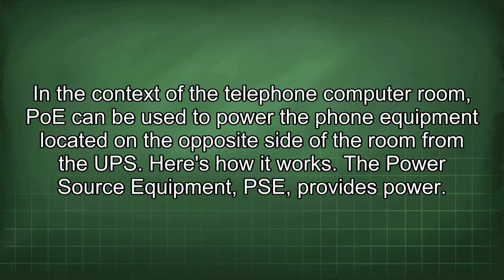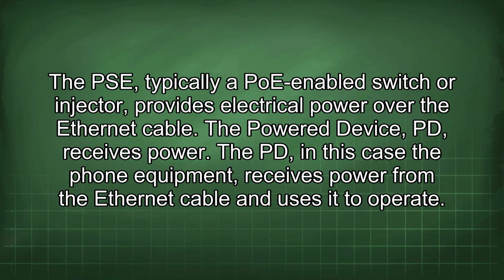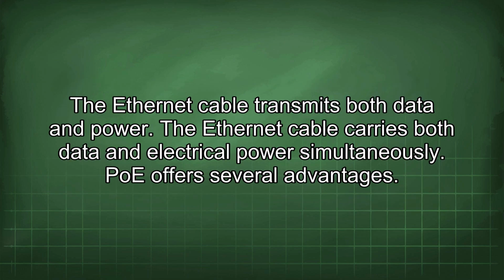Here's how it works. The power sourcing equipment, PSE, typically a PoE-enabled switch or injector, provides electrical power over the Ethernet cable. The powered device, PD - in this case the phone equipment - receives power from the Ethernet cable and uses it to operate. The Ethernet cable carries both data and electrical power simultaneously.